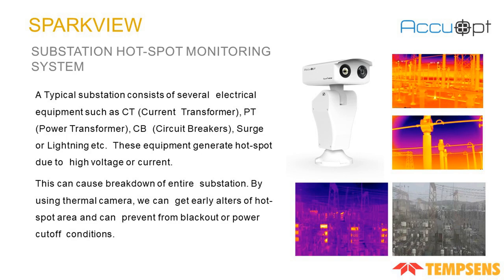This is SparkView system, dedicated to substation hotspot monitoring. In a substation, many electrical equipment such as current transformers and power transformers can generate hotspots due to high voltage current, which can cause the breakdown of the entire substation. By using our SparkView system, we can get early alerts of hotspots and prevent blackout or power cut conditions.